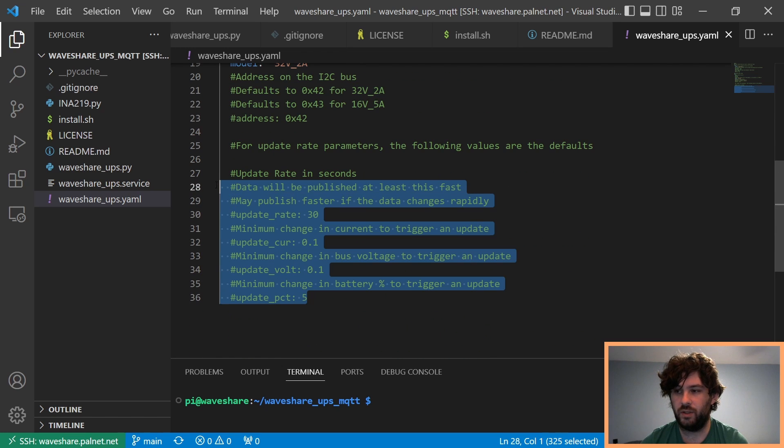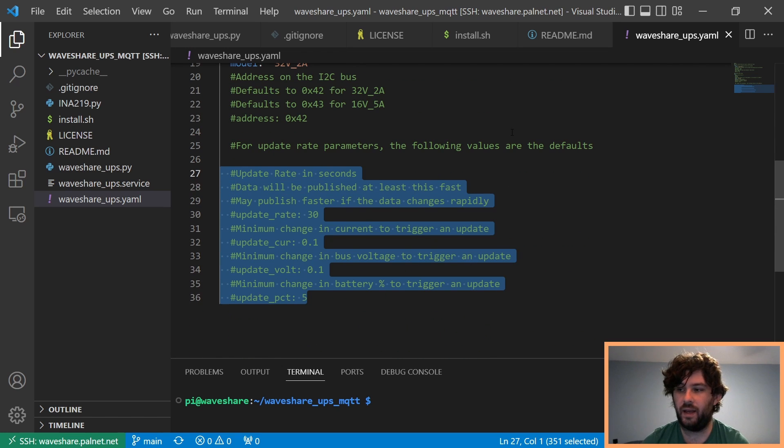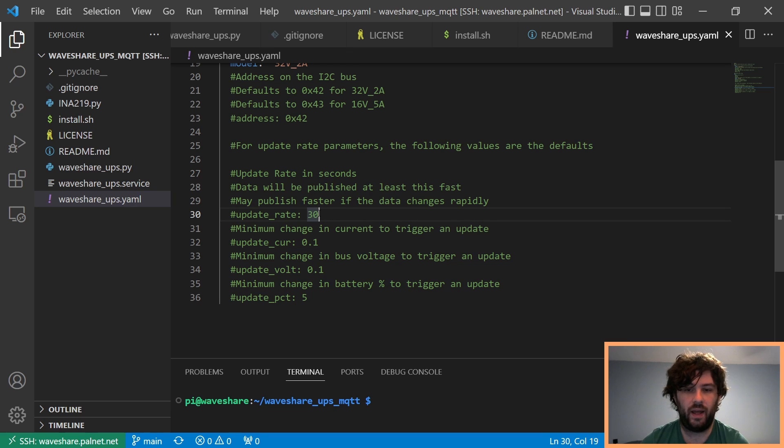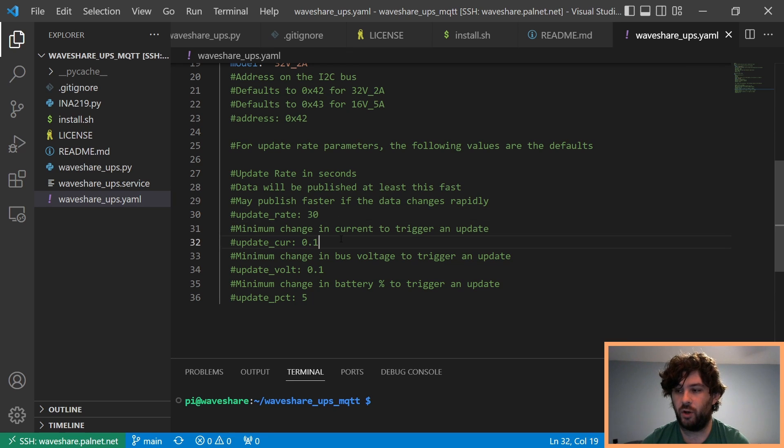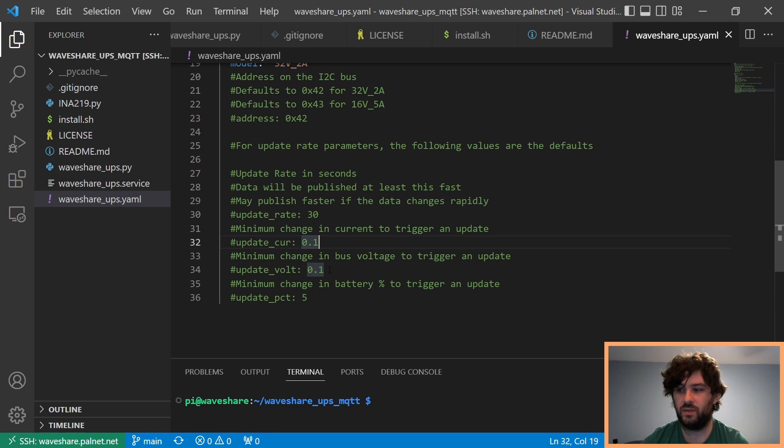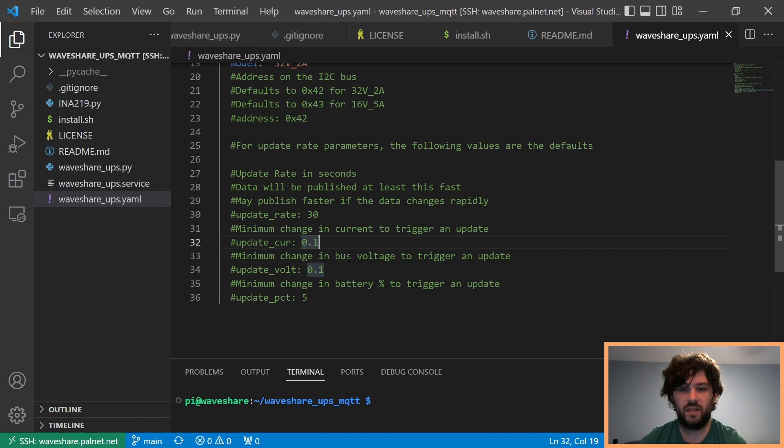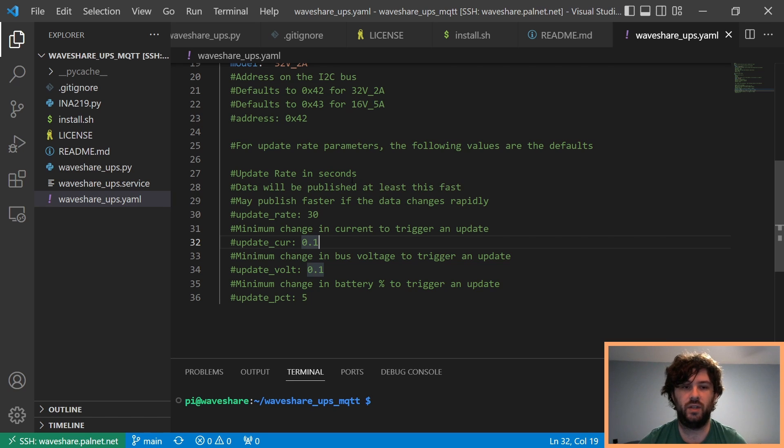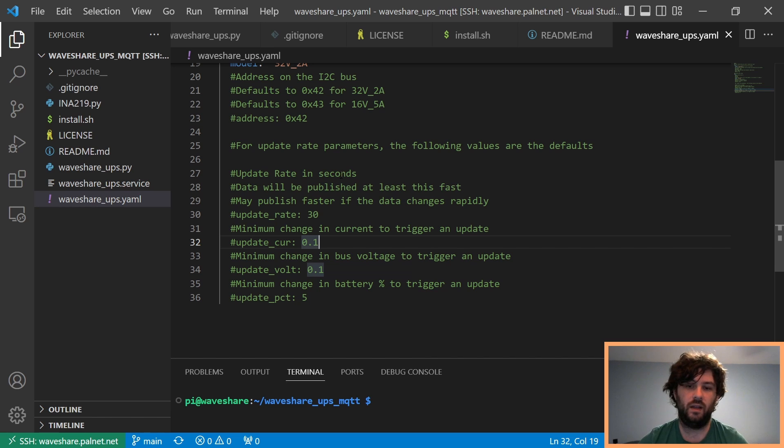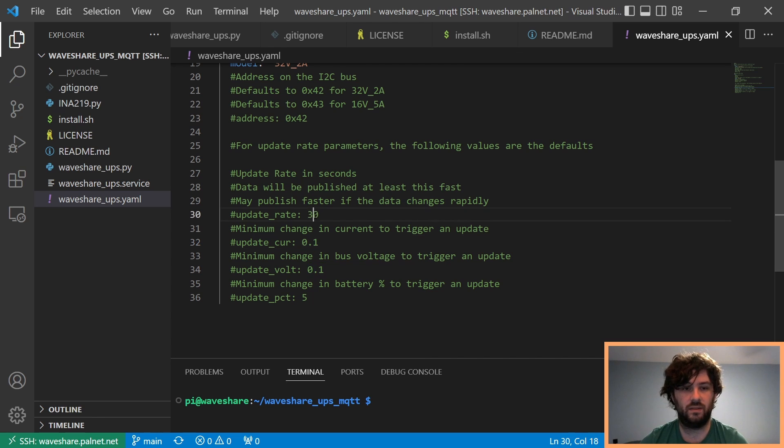And you can change how fast you want it to update. I, in my case, I defaulted it to 30, but I actually updated to 120 seconds. But then, if the current changes by more than 0.1 amps or any of these things change by more than this number, it'll send an update immediately. And it scans every one second. So, it's scanning every second and if it sees a change in current or voltage, it will send out an update immediately. And if it hasn't seen that change, it'll send out every 120 seconds, in my case, or 30 if you use the default.